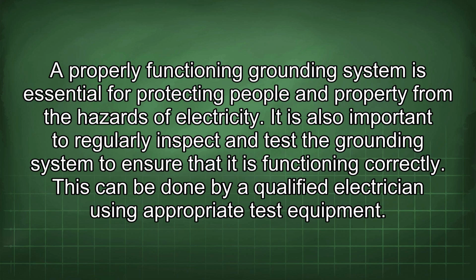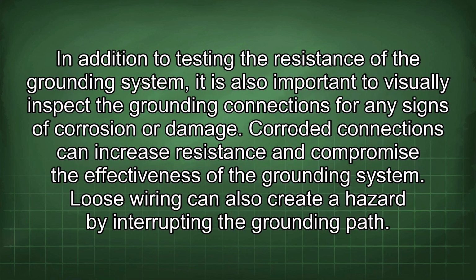This can be done by a qualified electrician using appropriate test equipment. In addition to testing the resistance of the grounding system, it is also important to visually inspect the grounding connections for any signs of corrosion or damage. Corroded connections can increase resistance and compromise the effectiveness of the grounding system. Loose wiring can also create a hazard by interrupting the grounding path.